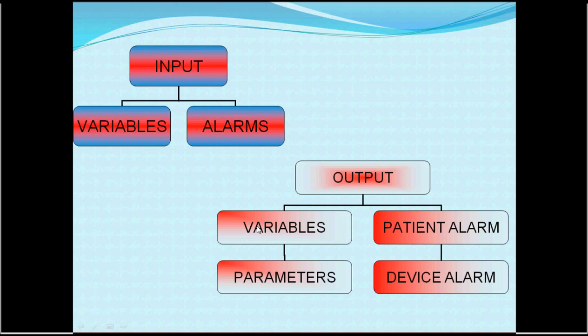The output for these variables comes out numerically and graphically. The output for the alarms is also displayed. In addition, there are calculated parameters as a function of the lungs and respiratory system — such as dynamic and static compliance, airway resistance, total minute volume, oxygen consumption, and carbon dioxide output. Finally, there are device alarms when something goes wrong with the ventilator circuits.